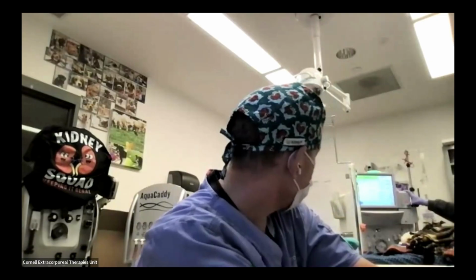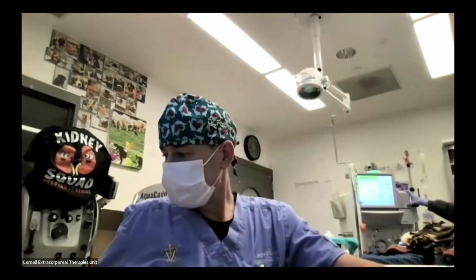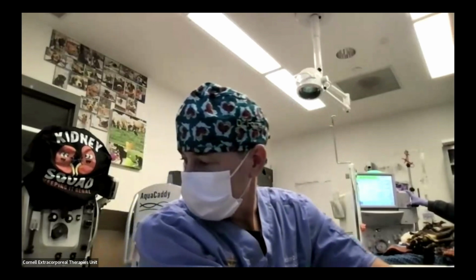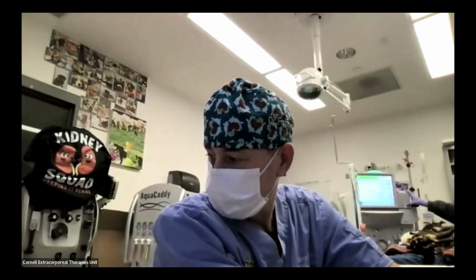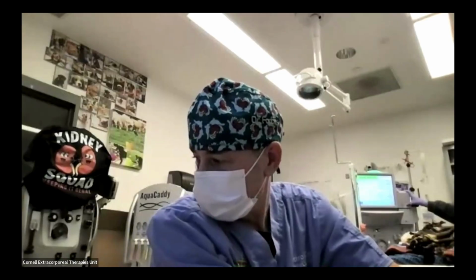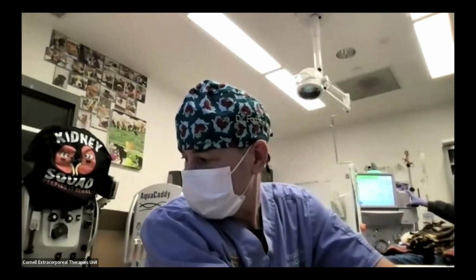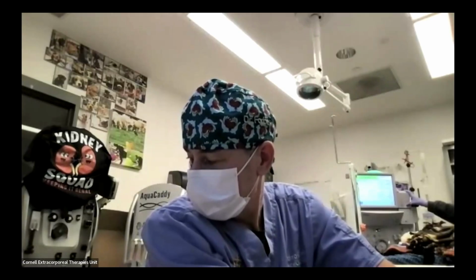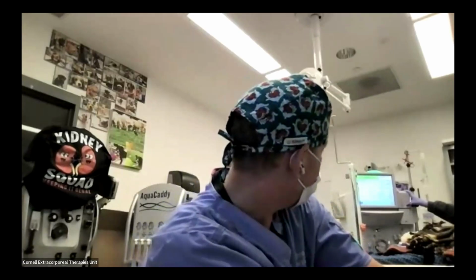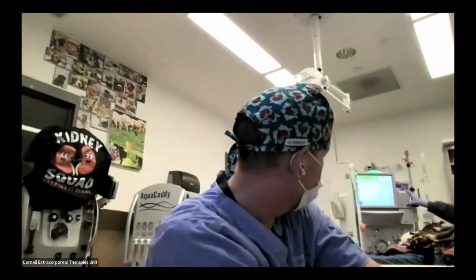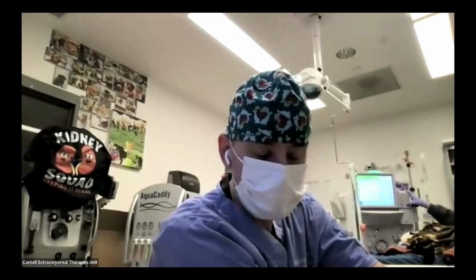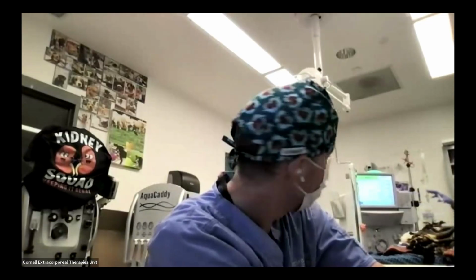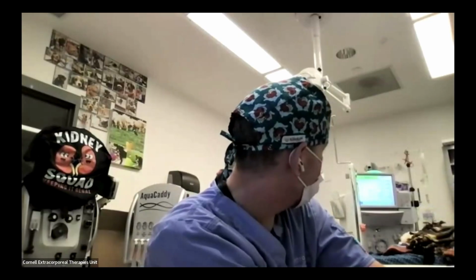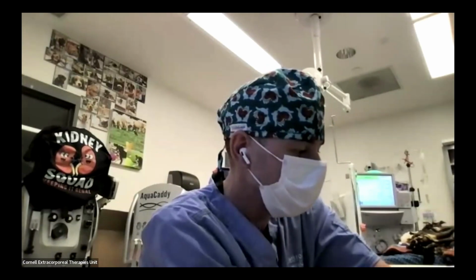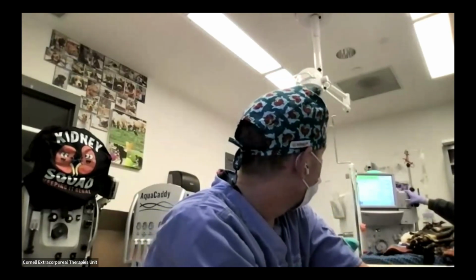We have 2.6 millimeter sets made by Medibron. It's got a priming volume of 29 mils, combined with the F3 dialyzer, which has a priming volume of 24 mils, plus our crit line. So we've got a fairly nice small blood volume in the circuit for this patient. But the platform has a couple of places where it gets upset. One is we've got consistent TMP, transmembrane pressure, alarms. I'm not doing any ultrafiltration, and then I do a little bit just to see if I can help move things. It's a low flux dialyzer, the F3. It's not meant to do a whole lot.